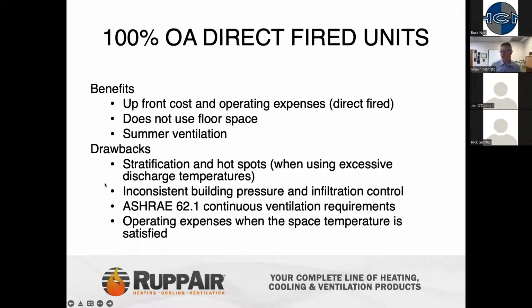Some of the drawbacks, like I said, when the unit is utilized as a cycling style system, you may have stratification or hot spots. Inconsistent building pressurization we've talked about, not being compliant to that ASHRAE 62.1 or the IMC codes. And operating can be expensive when the space temperature is satisfied, meaning we're going to overheat or overpressurize the space if that VFD is not in play.